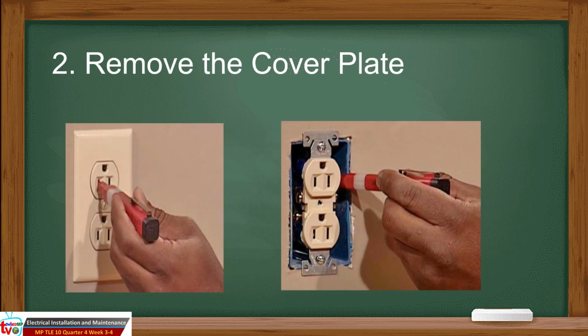Remove the cover plate. Use a tester to make sure the power to the outlet is indeed turned off. Remove the screw holding the cover plate and take the plate off. Then test the outlet again. Be sure to use the tester to probe all around the box to make sure there is no juice at all.